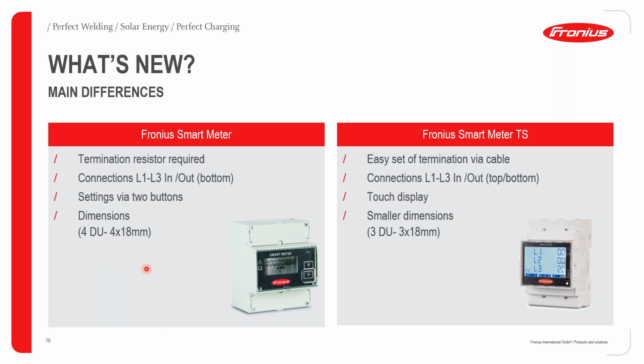And the other major difference would be the dimension units. The older version of the smart meter is slightly bigger than the new version. So we can see here that we have 3 dimension units for the smart meter TS, the touch screen, and then we have 4 dimension units for the older version smart meter. Therefore, when you're installing this new smart meter into a control panel somewhere, you require slightly less space than the older version.